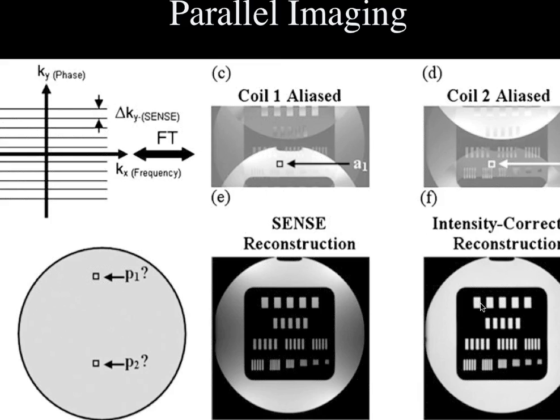What parallel imaging does — and there are many different ways to do this — is take less time by requiring fewer lines of k-space, which leads to wrapped images. We can then unwrap them using mathematical equations that exploit the spatial information from the phased array coils to create unwrapped images. There are many mathematical tricks to do this; they're all variations on this same theme.